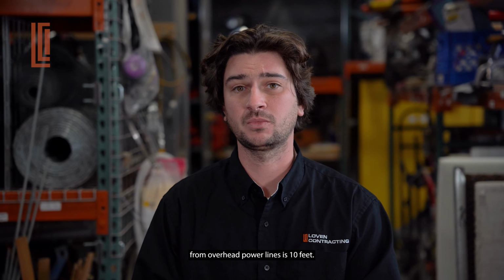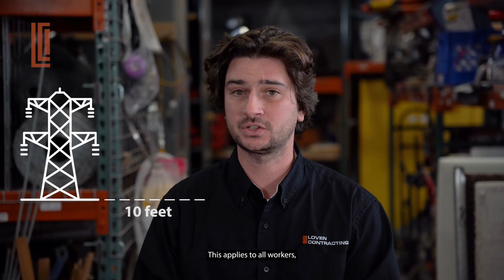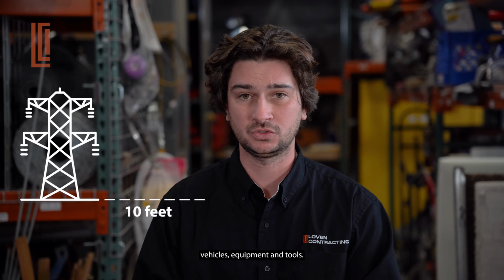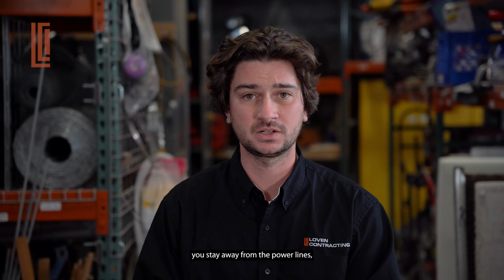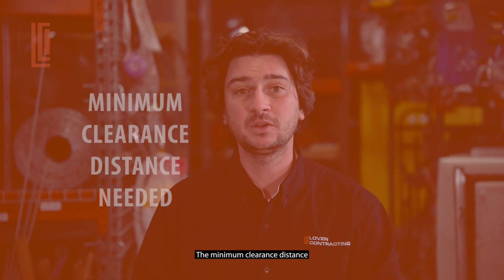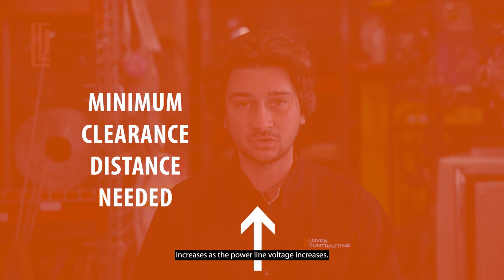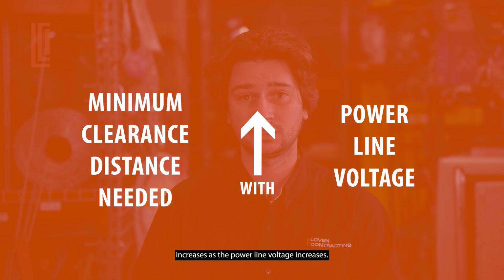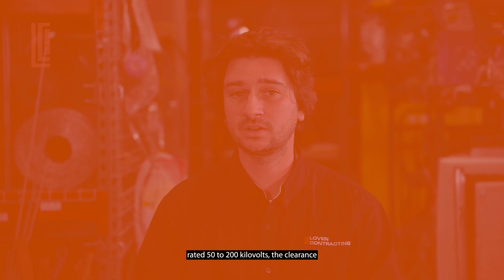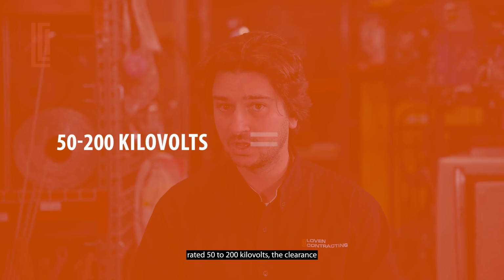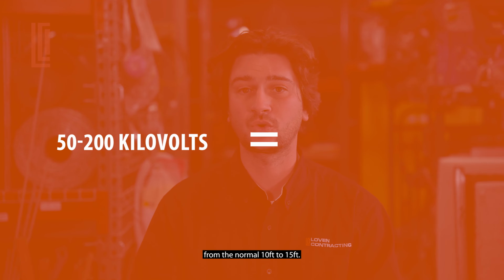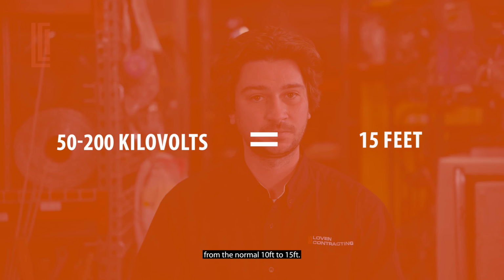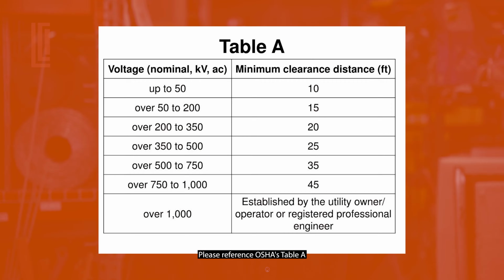The minimum safe distance from overhead power lines is 10 feet. This applies to all workers, vehicles, equipment, and tools. The further you stay away from the power lines, the lower the risk of a contact accident or non-contact electrical arc. The minimum clearance distance needed for protection increases as the power line voltage increases. For example, for lines rated 50 to 200 kilovolts, the clearance distance increases from the normal 10 feet to 15 feet. Please reference OSHA's Table A for required distances when working with high voltage lines over 50 kilovolts.